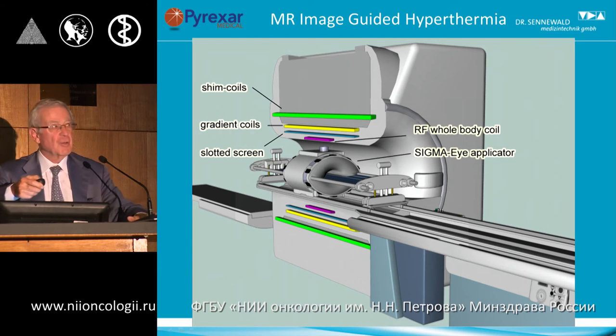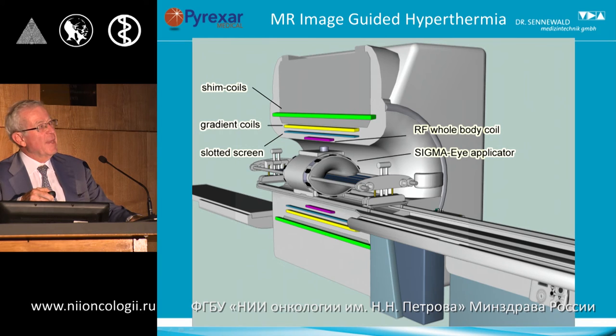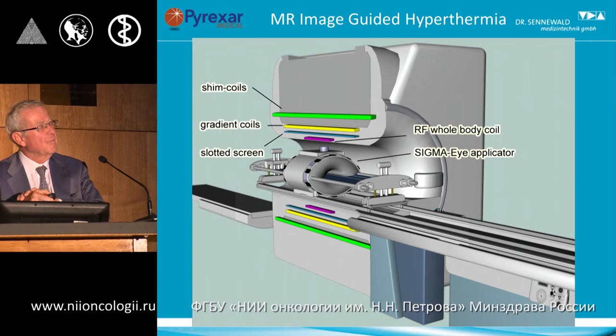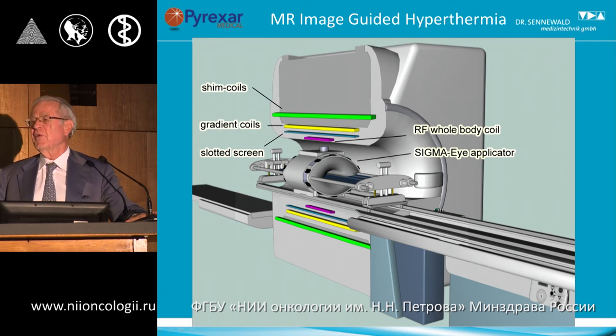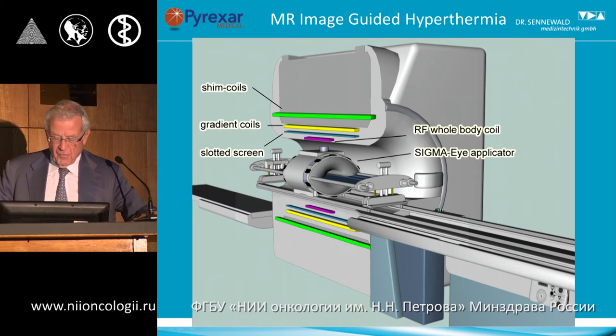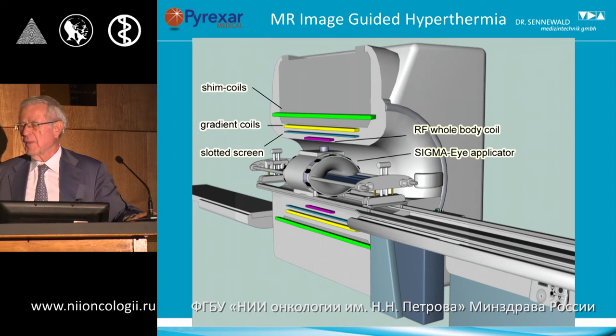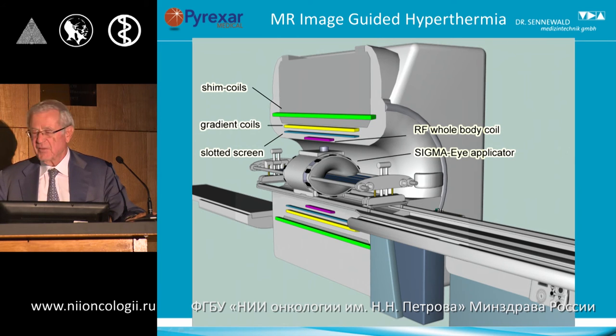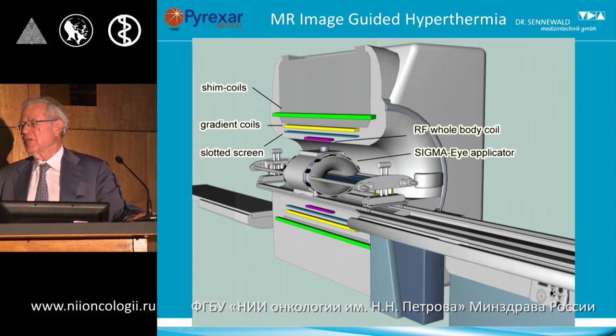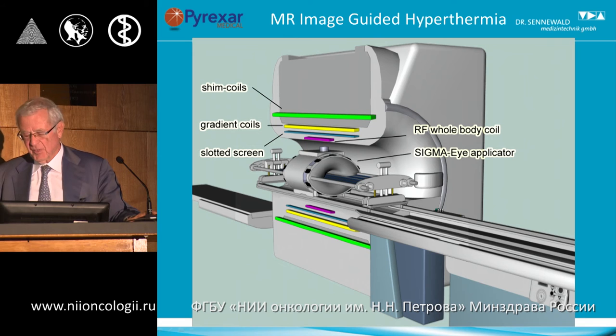It is particularly important that the isocenter of the magnet tunnel and the applicator are the same. At the time this was fairly easy to achieve because the magnet diameter was 60 cm and the applicator barely fit inside the 60 cm tunnel — so by mechanical engineering necessity, the device fitted nicely in the isocenter of the system.